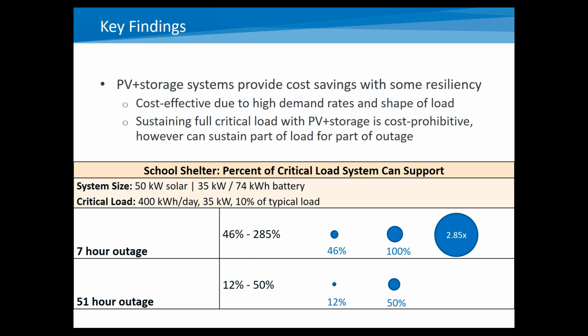So you can save on your costs through the demand charge reductions, depending on the shape of the load. But sustaining that full critical load with PV and storage, as Kate mentioned, was pretty cost prohibitive. This example is different from the fire station, which Kate reviewed. This is from the school shelter. And this site was an interesting comparison because whereas the fire station had a very small roof space, so minimal PV, and a very high critical load because of the important function that a fire station provides, the school shelter had a lot of roof space and a relatively small critical load.